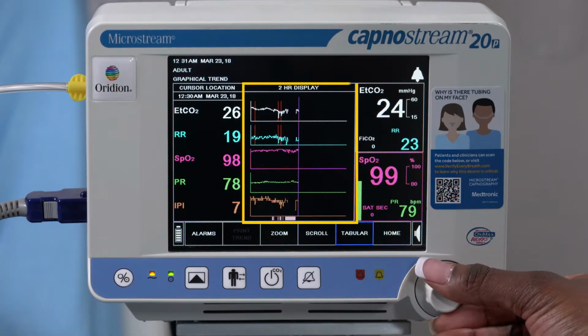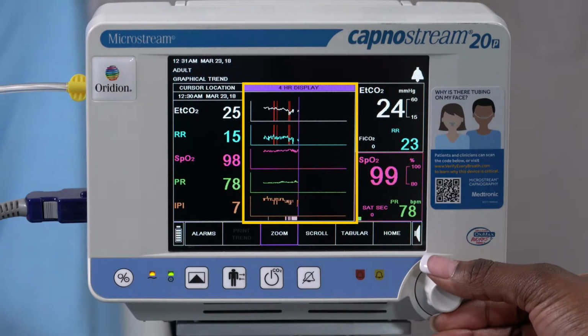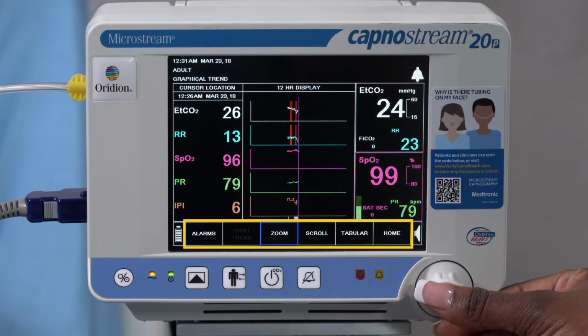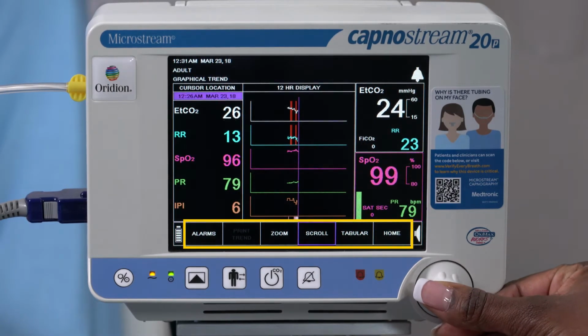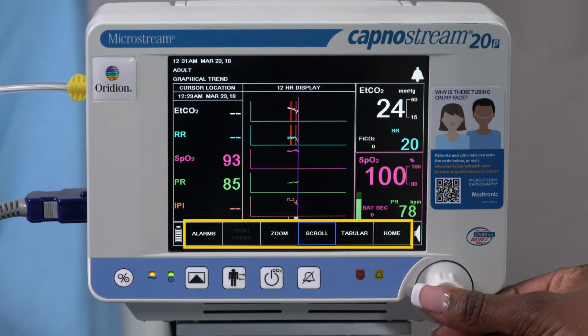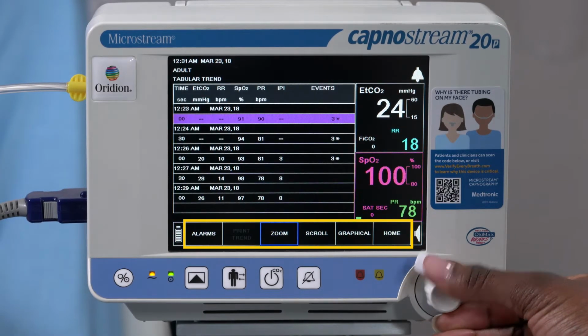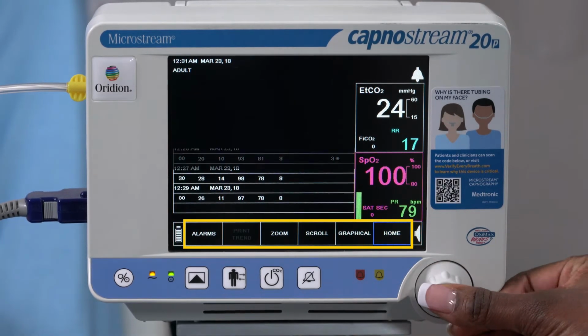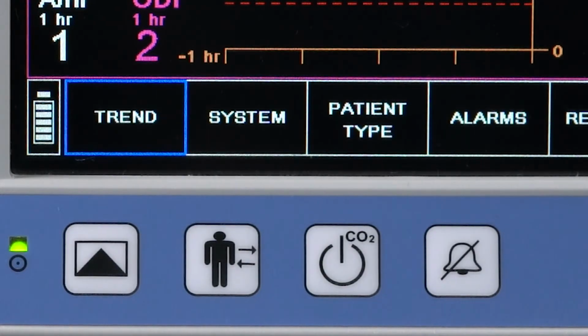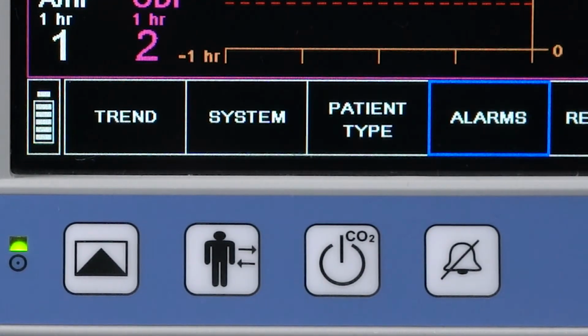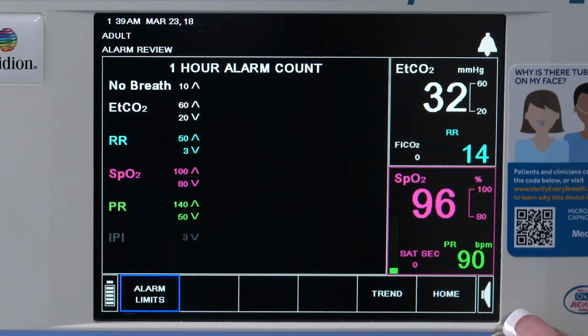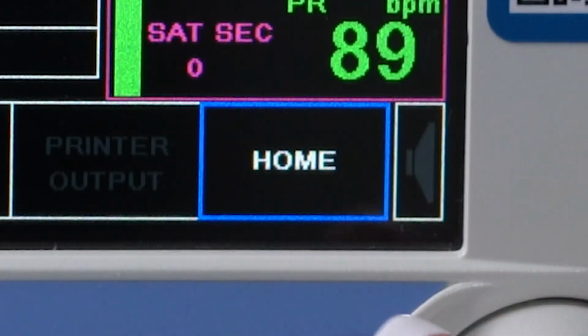You can zoom from a 2, 4, or 12-hour display. To scroll through the trend, highlight the scroll tab and press the control knob. For a tabular trend, highlight the tabular tab and press the knob. Press home to return to the main screen. If you want to see the alarm count, scroll to the alarm tab and push the knob. It will highlight the alarms and what measurements they're associated with for the past hour. Don't forget to press home to save the settings. Please refer to your hospital's policy for any alarm setting changes.